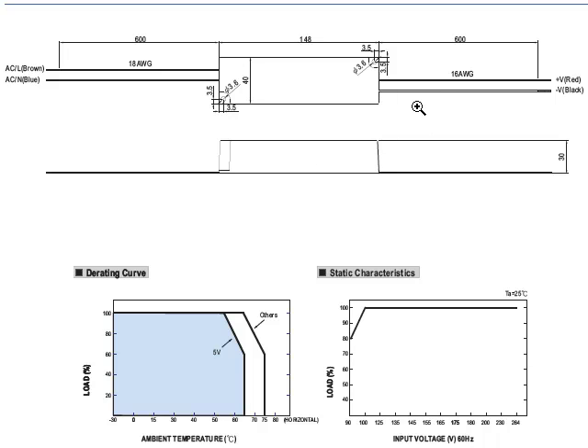If you download the specification you will see the complete mechanical outline drawing as well as the derating curve, showing that this power supply will operate roughly up to full load at almost 65 degrees C, derating to 60 degrees or 60 percent total power at 75 degrees C.